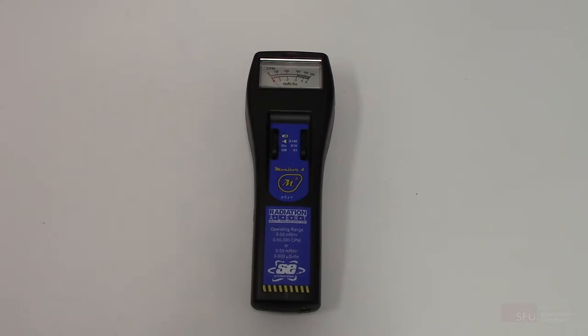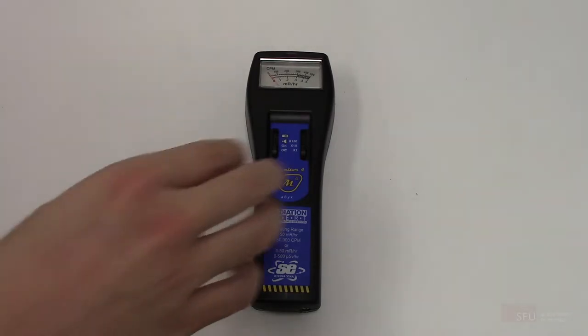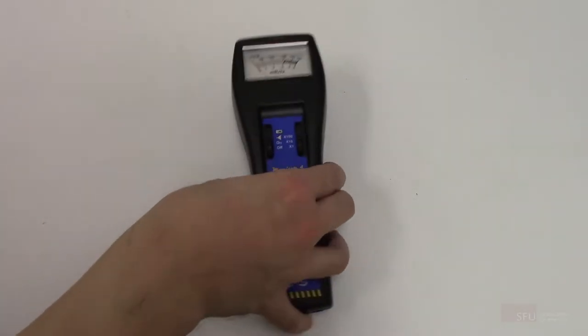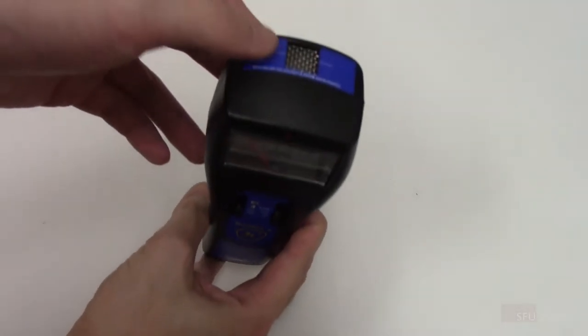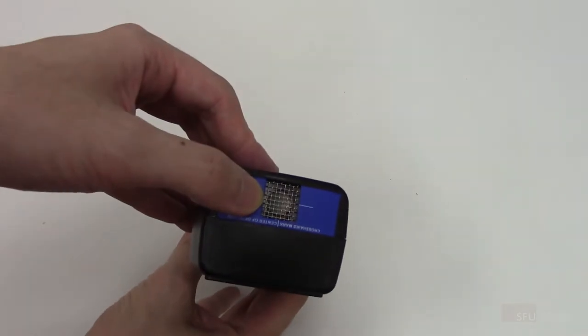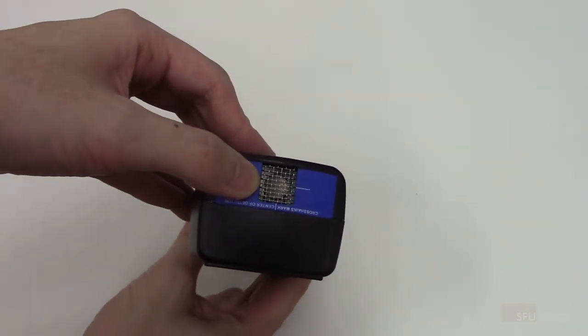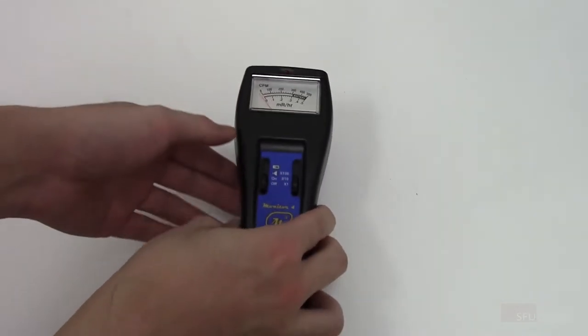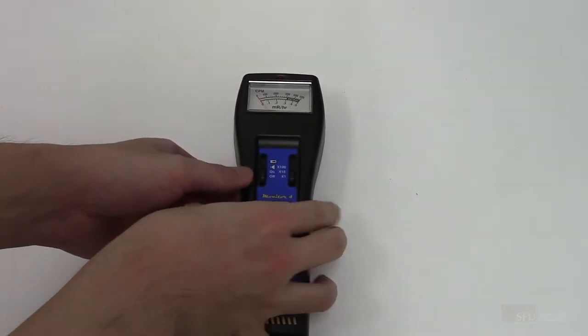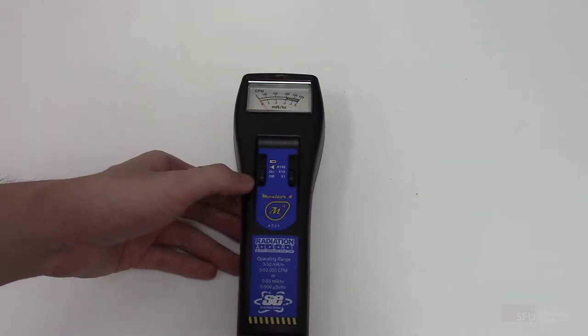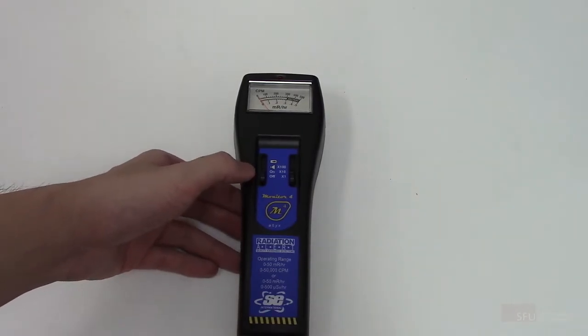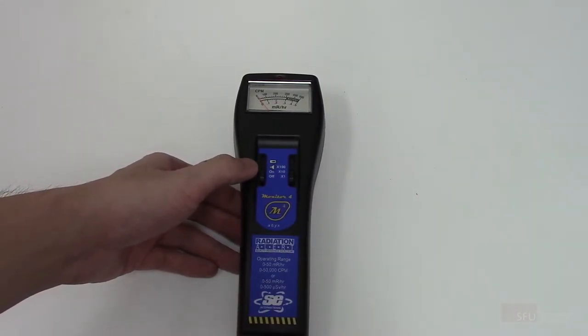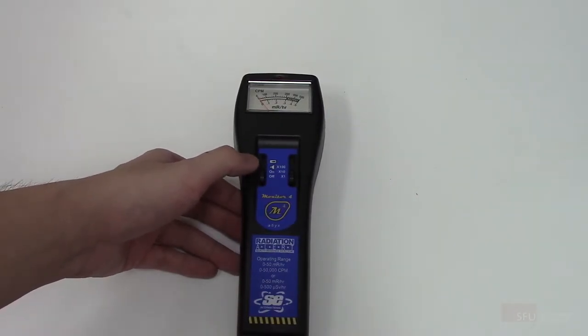The Geiger counter senses particles that make it through a thin and delicate mica window on top here. The physical controls on the Geiger counter on the left are off, on, audio counts, and battery test switch settings.